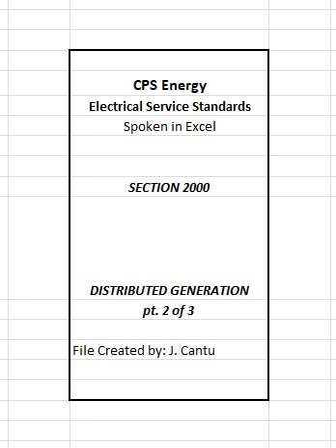4. Meter socket terminals are designed to accept either copper or aluminum conductors. 5. All wire ends must be wire brush cleaned. The wire brushed ends and terminals used with aluminum conductors shall have grit-filled joint compound applied to them before the terminal screws are torqued. 6. Customer must observe the terminal screw torque requirements. 7. Conductors formed within the socket's enclosure shall not rest on or press against other terminals. Note: in no case should customer connect PV system in parallel with CPS Energy source supply without first having a commissioning performed and written express consent of CPS Energy.